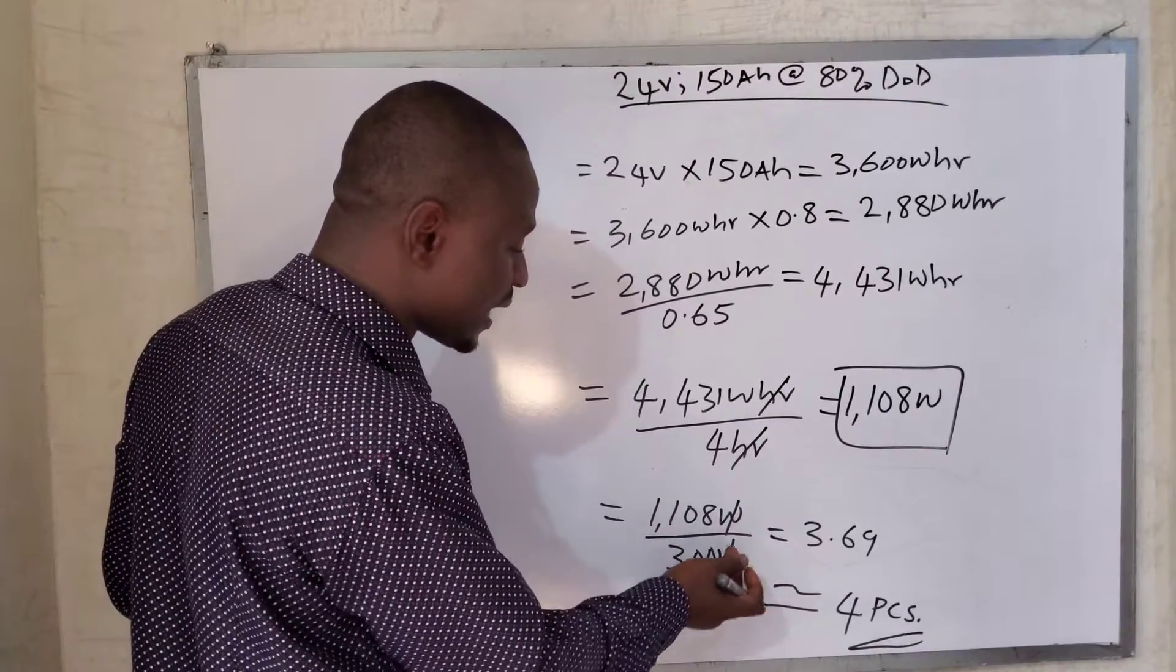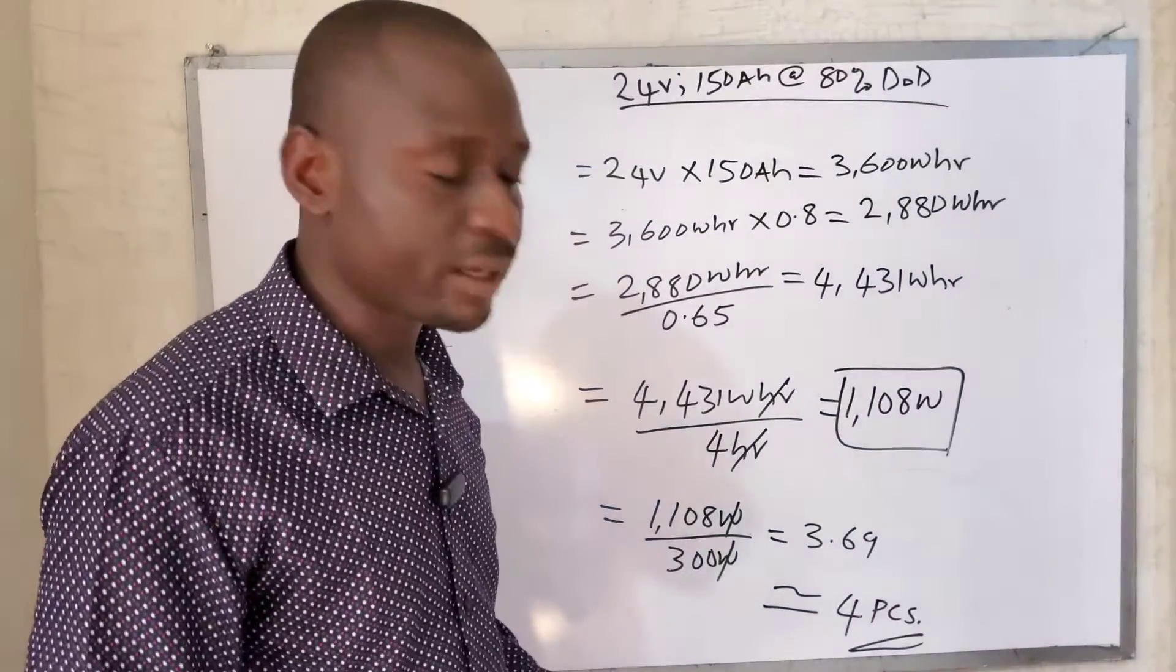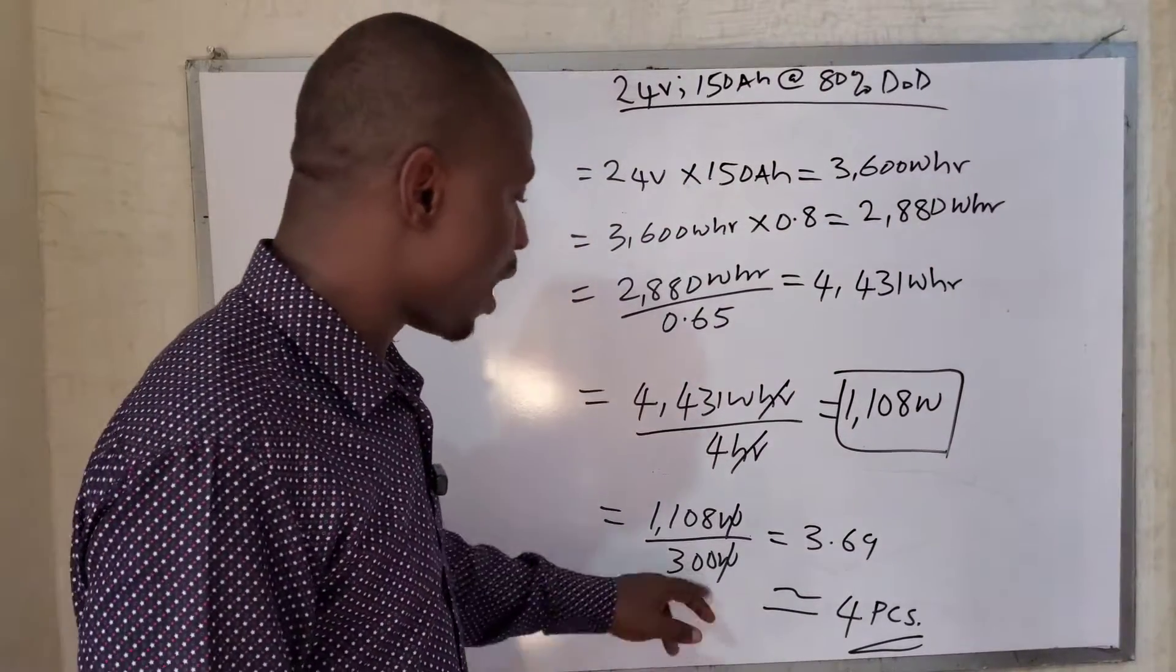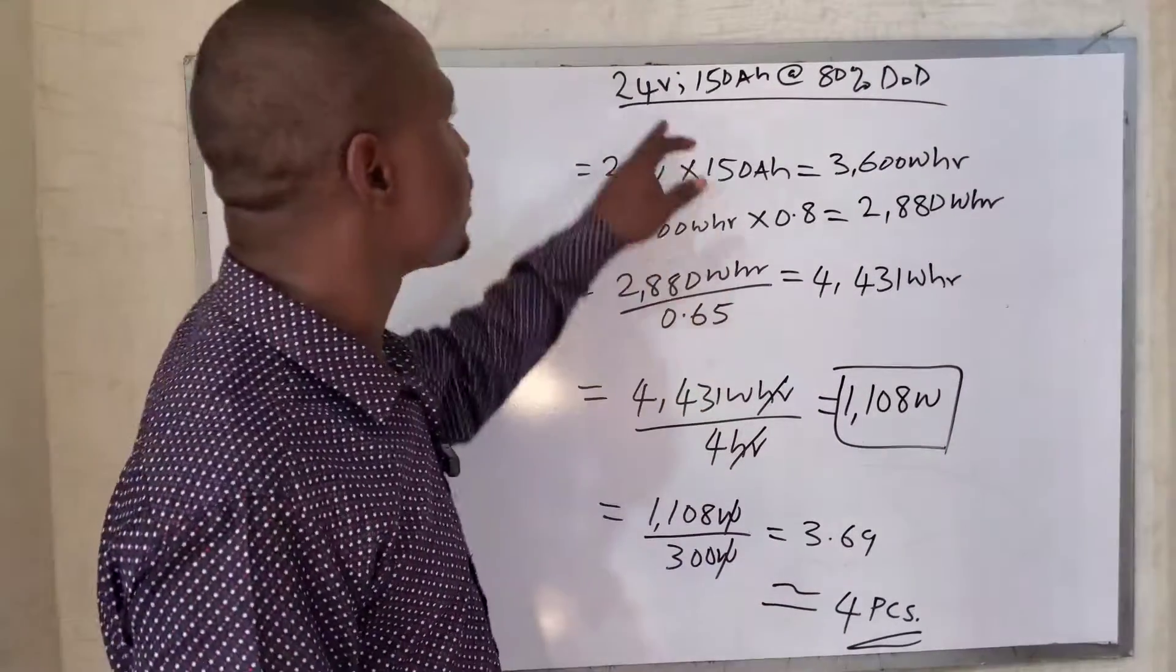1,108 watts divided by 300 watts - the watts will cancel - we'll have 3.69 panels, approximately 4 pieces of 300-watt solar panels to charge our 24-volt 150 amp-hour battery bank at 80% DoD.